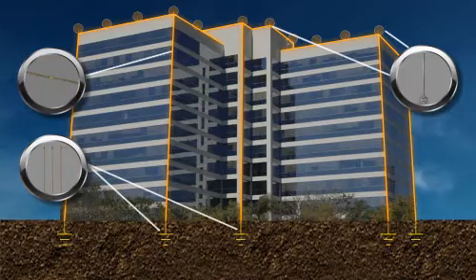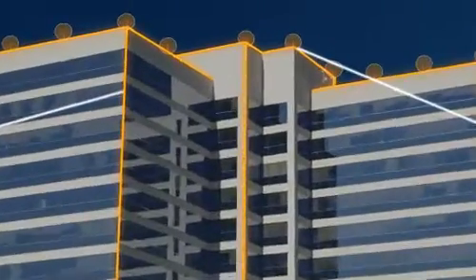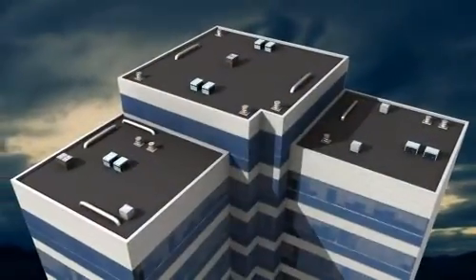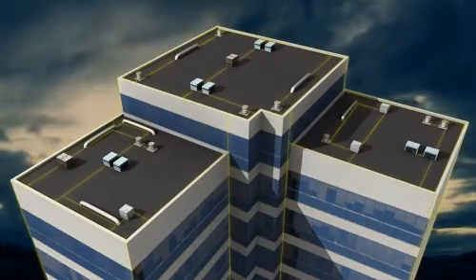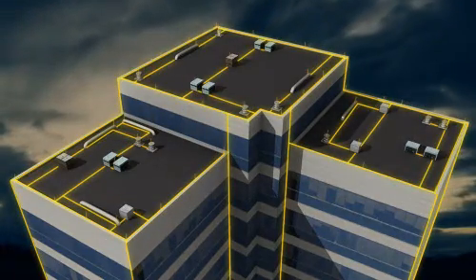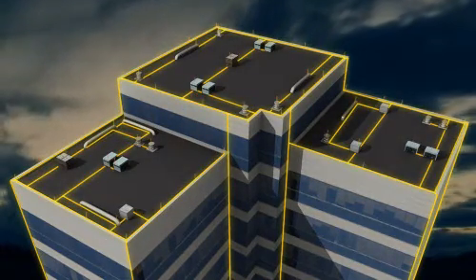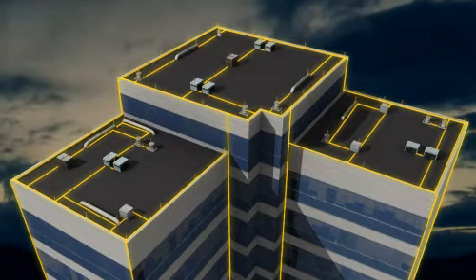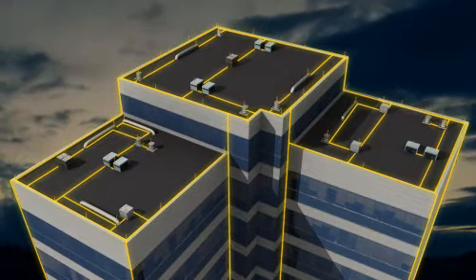On a flat roof structure, this interconnected system is also routed through the mid-roof areas and bonded to the required rooftop mechanical equipment, such as air conditioning units, exhaust fans, plumbing vents, roof drains, and roof ladders.